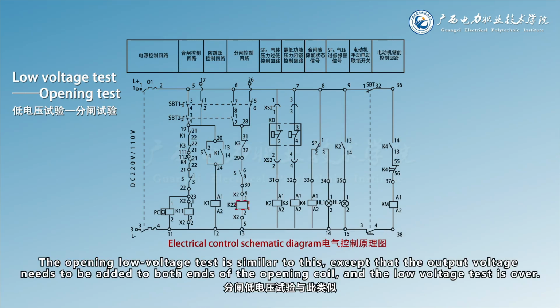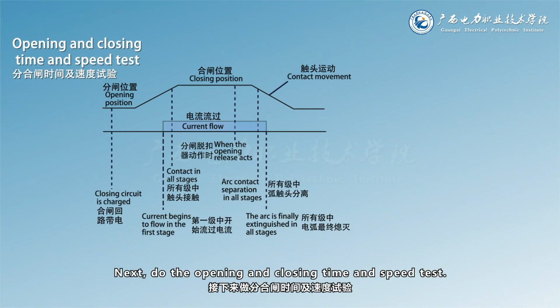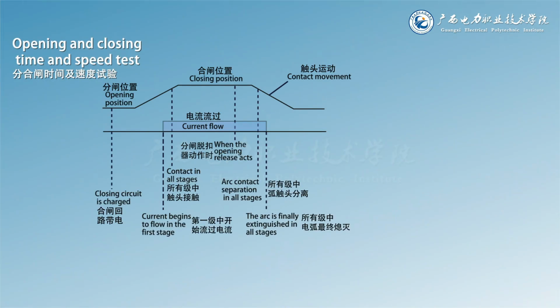The opening low voltage test is similar to this, except that the output voltage needs to be added to both ends of the opening coil, and the low voltage test is over. Next, do the opening and closing time and speed test.